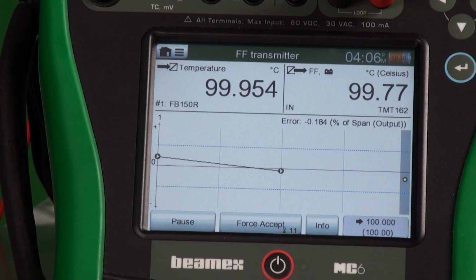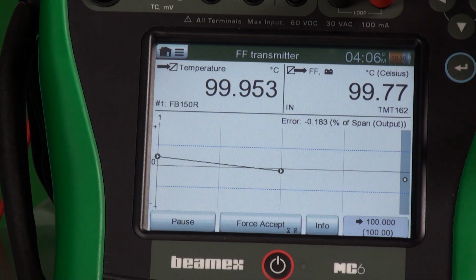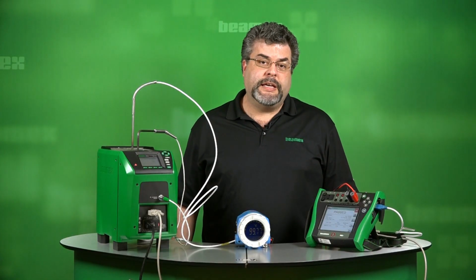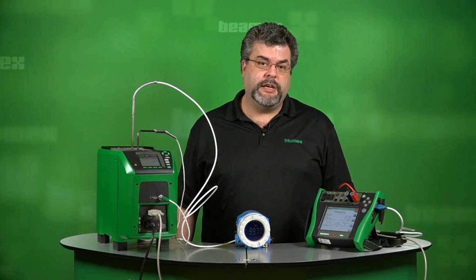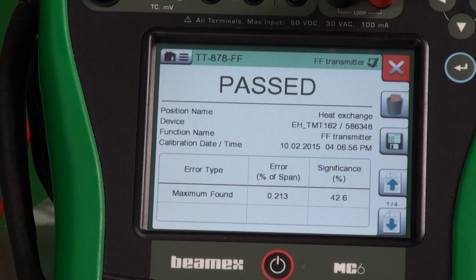We've reached the final test point. As you can see, the dot is a little bit below on the graph. We can see our error tolerance. We're at negative 0.182% of span error. Once we get the final test point, then we show that it is passed. At the bottom, we can see our maximum error.